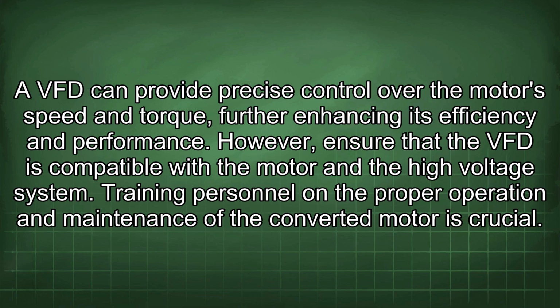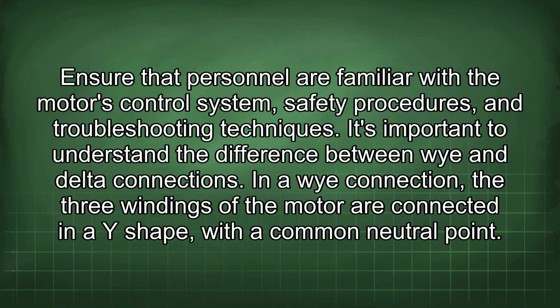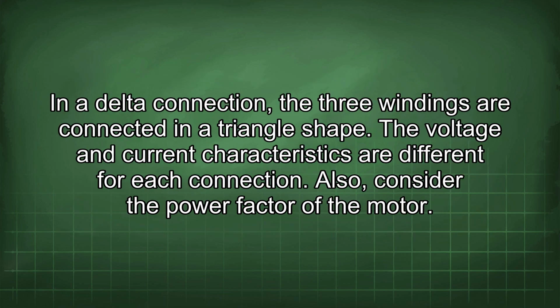Training personnel on the proper operation and maintenance of the converted motor is crucial. Ensure that personnel are familiar with the motor's control system, safety procedures, and troubleshooting techniques. It's important to understand the difference between Y and delta connections. In a Y connection, the three windings of the motor are connected in a Y shape with a common neutral point. In a delta connection, the three windings are connected in a triangle shape. The voltage and current characteristics are different for each connection.